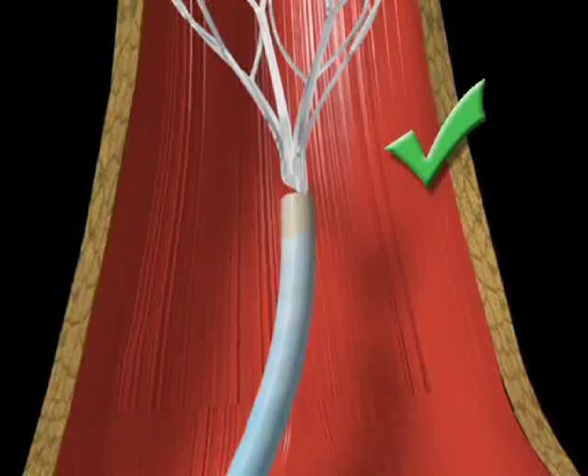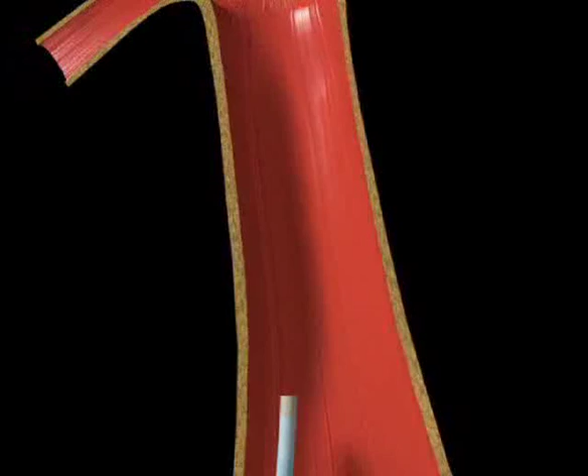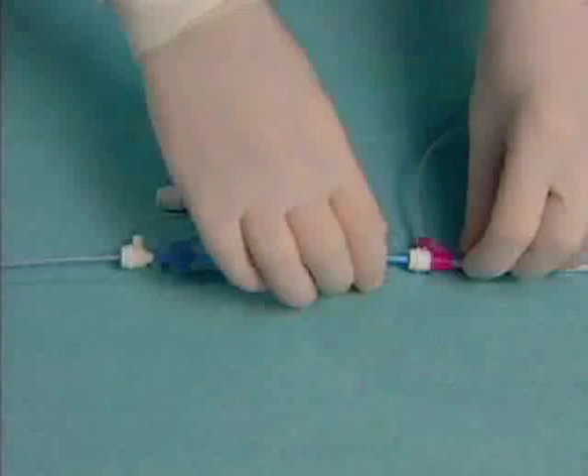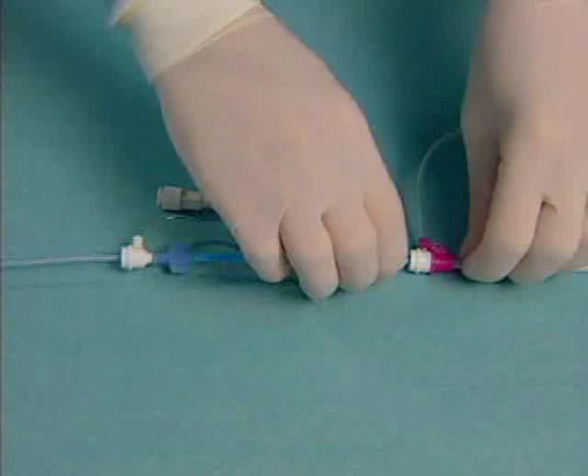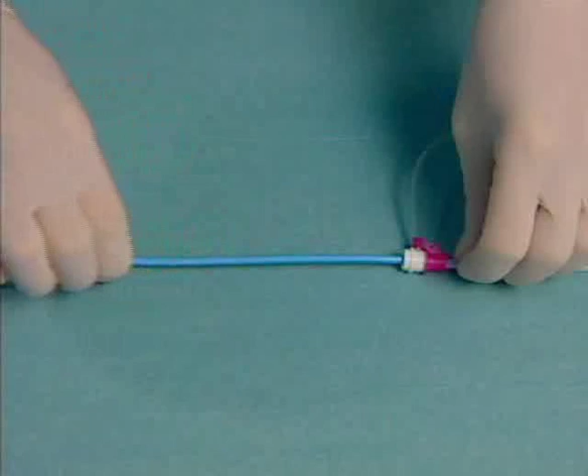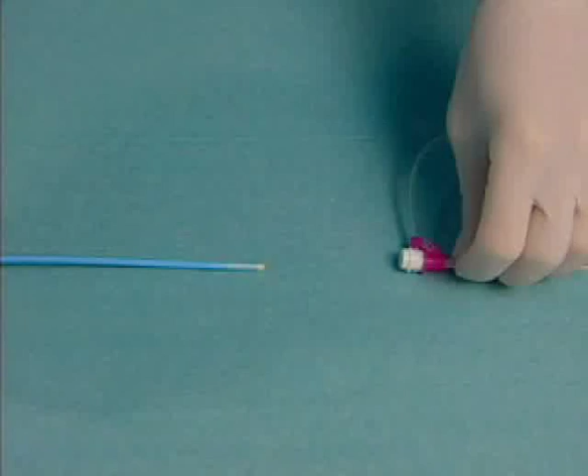While keeping tension on the snare, hold the retrieval catheter stationary and withdraw the filter into the retrieval catheter by retracting the endovascular snare. Continue retracting the snare until the filter is completely collapsed inside the retrieval catheter. Once the filter is fully collapsed inside the OPTEASE retrieval catheter, retract the complete system as a unit out through the 10 French catheter.